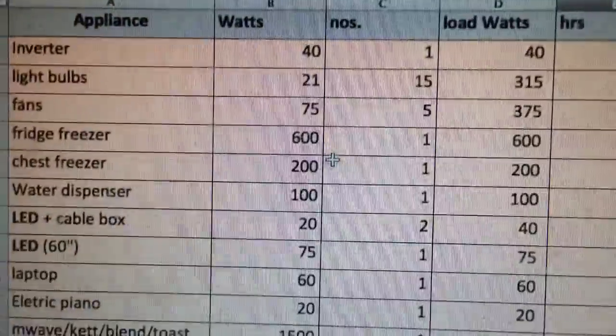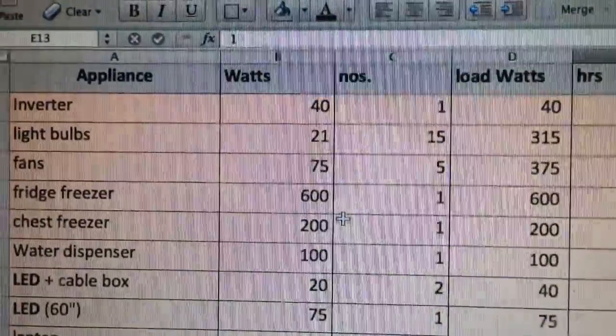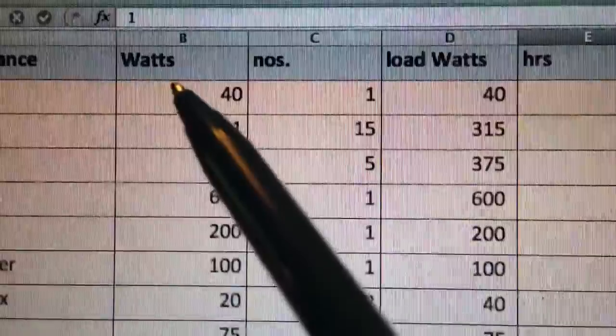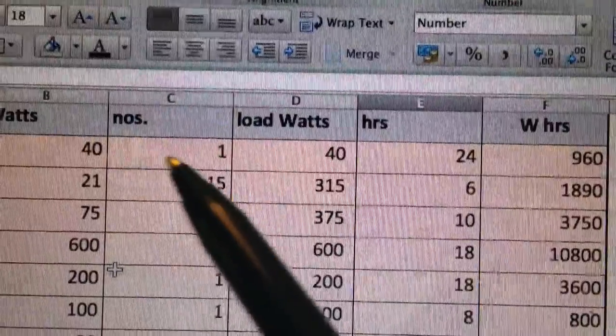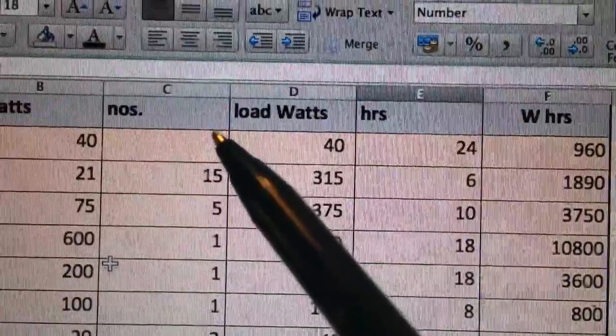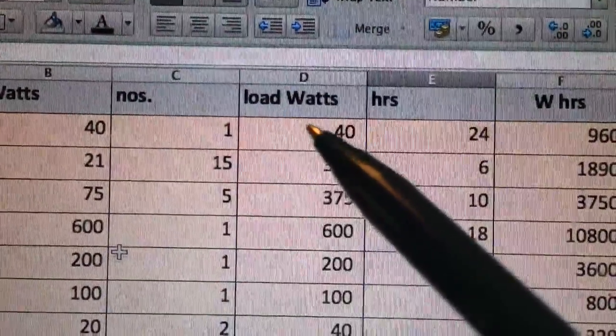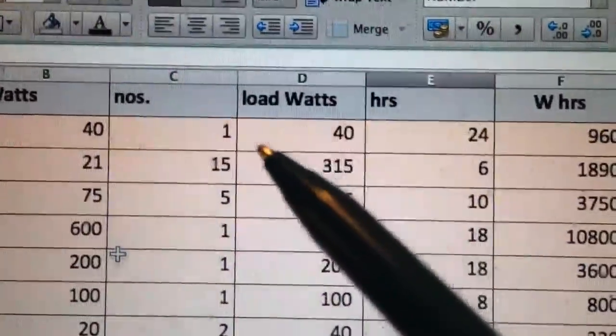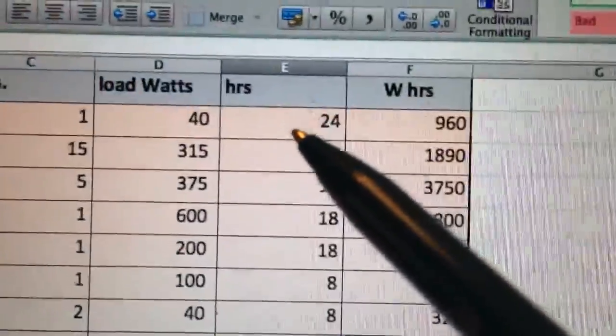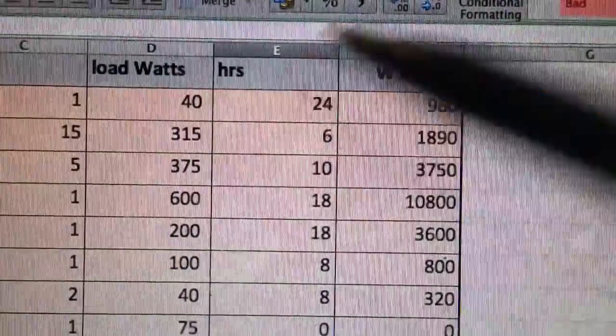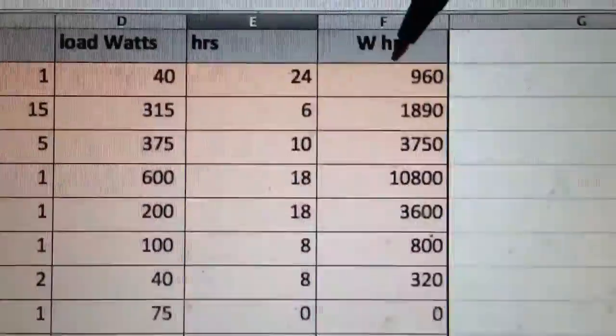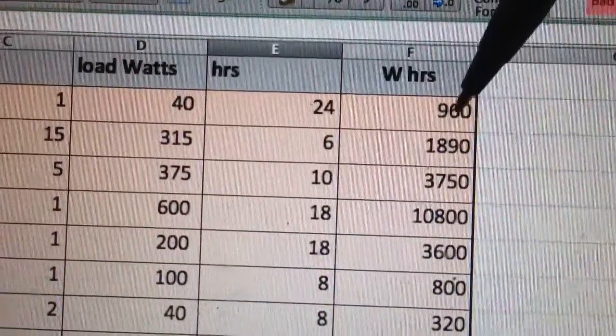So this is my energy survey. At the top you've got the appliance, how many watts the appliance uses, how many of the appliances you have. Multiply those two to get the number of watts all of such appliances are consuming, and how many hours they're on for to give you the watt hours in the last column.